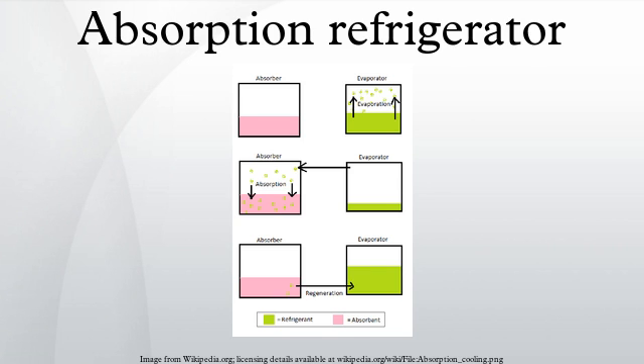The next step separates the ammonia and water. In the generator, heat is applied to the solution to distill the ammonia from the water. Some water vapor and bubbles remain mixed with the ammonia. This water is removed in the final separation step by passing it through the separator, an uphill series of twisted pipes with minor obstacles to pop the bubbles, allowing the water vapor to condense and drain back to the generator.